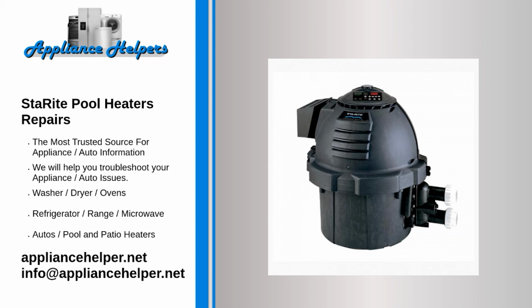Ensure the gas line valve is open and unobstructed. See above for more information about checking gas lines. The high limit switch is being activated. The high limit switch might be getting activated due to overheating caused by poor ventilation or the heater being overworked due to improper sizing. The remedy is a larger heater or supplementing with a solar-powered pool heater, electric heater, or heat pump pool heater.